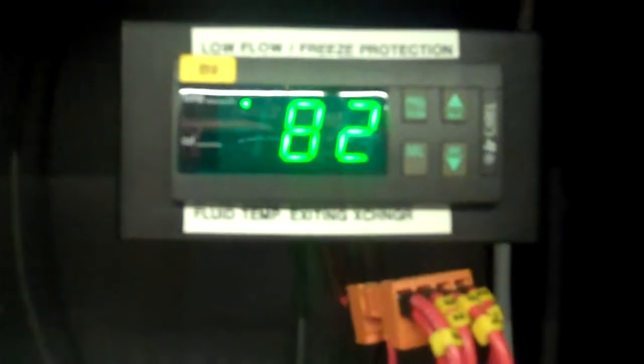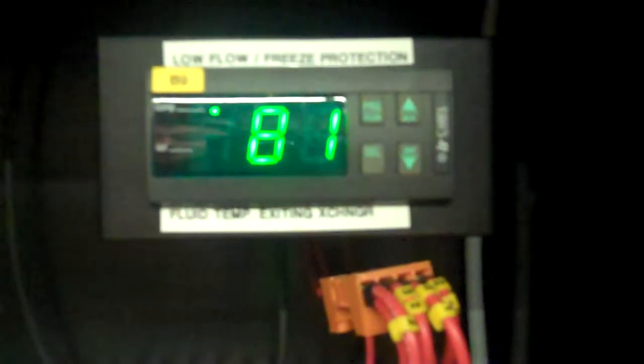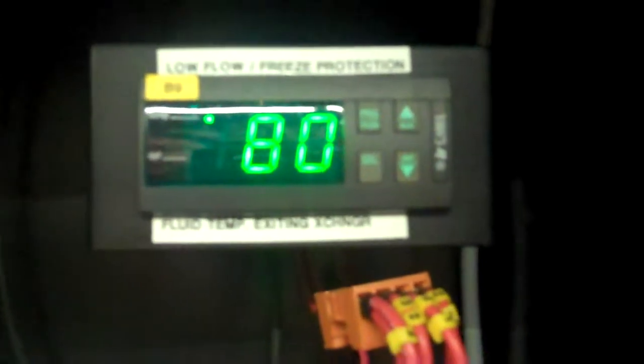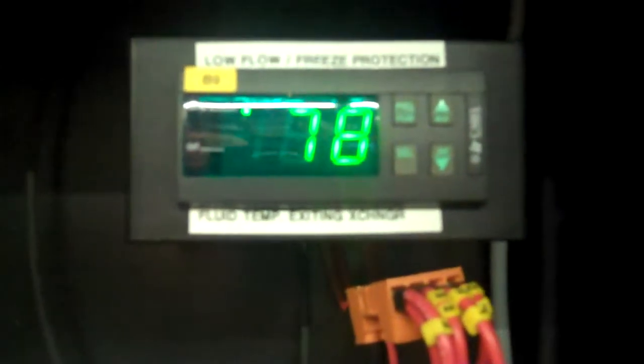So we do have the cover off right now. And show you a couple things in here. The controller transformer. This is our low flow, and you can hear the compressor just turned on. This is our control for low flow freeze protection. It's basically showing you the fluid temperature that's exiting the exchanger. Basically, in lieu of a flow switch, if it sees the fluid leaving the exchanger at too low of a temperature, which is basically what happens when there's no flow, it's going to shut the system down.